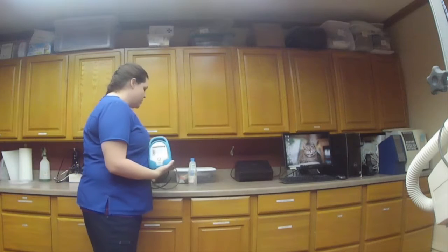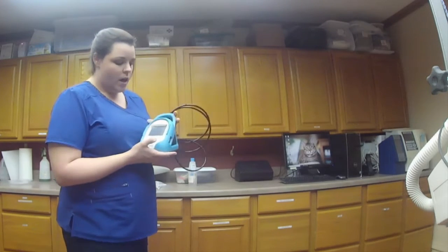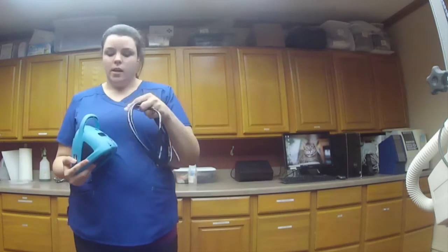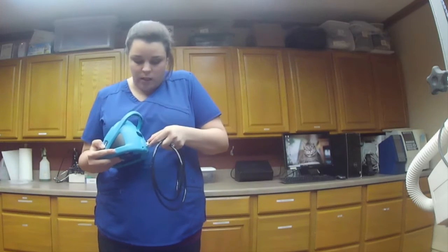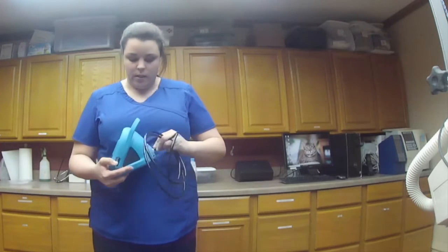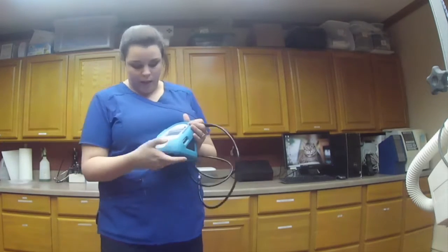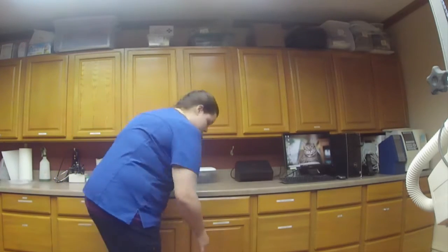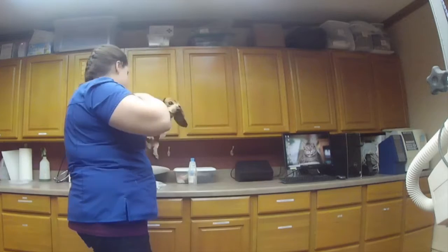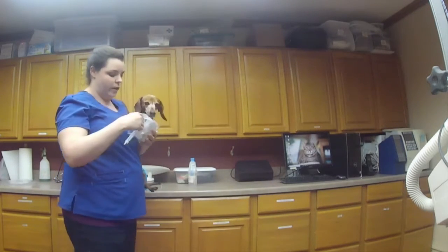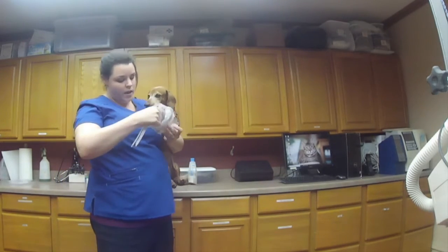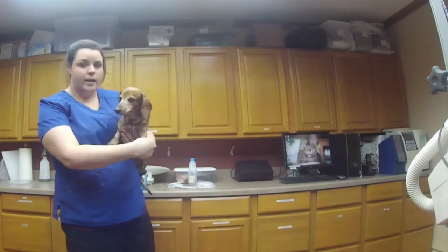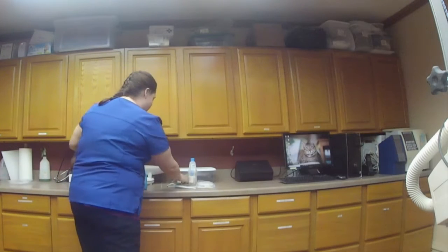Okay, so this is our blood pressure monitor. What you do is connect this hose to the back of the machine here, and it snaps in. That's how you know it's connected. You will pick either a dog or a cat, and there are several different cuffs in here, and you will base it on the size of the dog's leg.